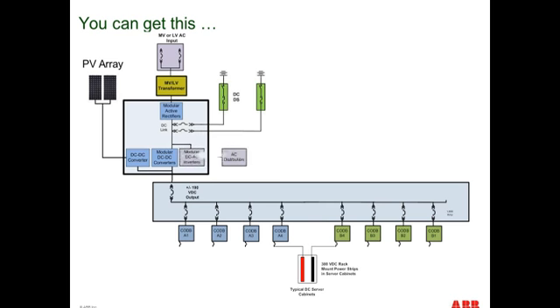You can also extract flexibility out of the system because we have the makings of an online double conversion UPS in this topology. We often hear, what if I have some parasitic AC loads I need to power? We could easily provide an inverter module in this system to power AC components throughout the data center. So DC enables a tremendous amount of flexibility in the types of sources we can integrate, the levels of reliability we can achieve, and there are really no limits to the engineering topologies we can deploy.